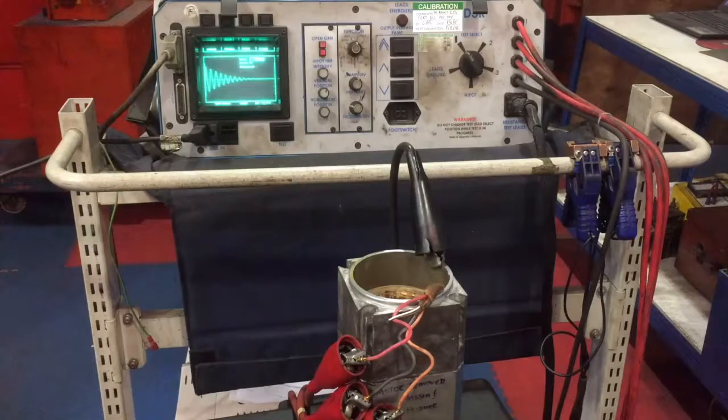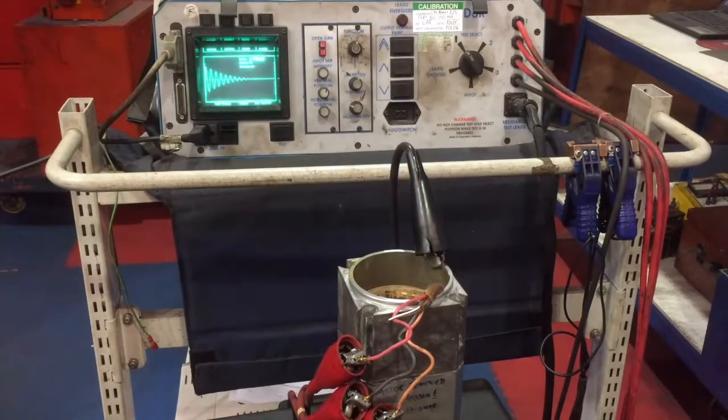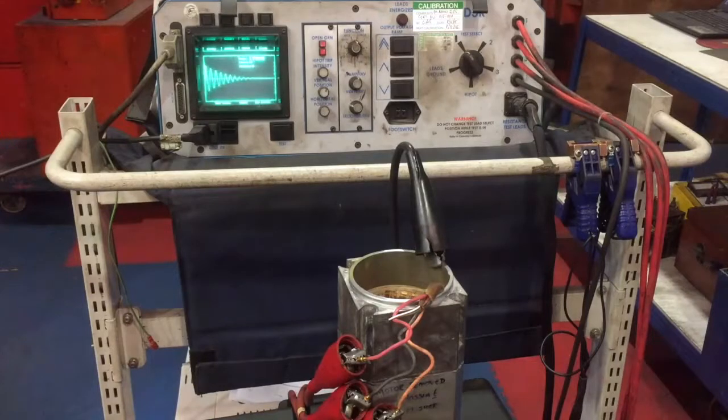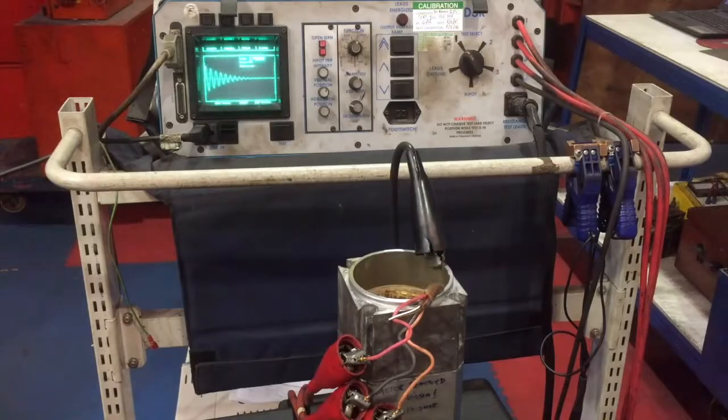To ensure reliable operation, we need to check the integrity of the stator windings. What we are doing here is carrying out a surge to surge comparison test on the windings. What we are looking for is turn to turn shorts between phases. Once this test has been carried out and we are happy with the state of the windings, we will then carry out a high potential test to earth. This will ensure the entire insulation system is correct, the windings are okay and fit to go back into service.